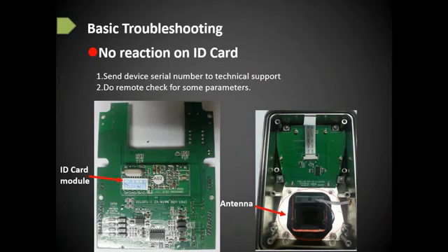If the parameter is okay, but there is still no reaction on the ID or MIFARE card, you can replace a new mainboard to test. I think it's helpful. 99% it will solve these problems. No reaction on ID card, MIFARE card, okay?